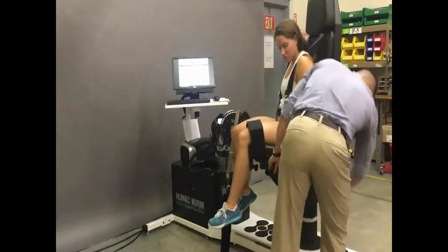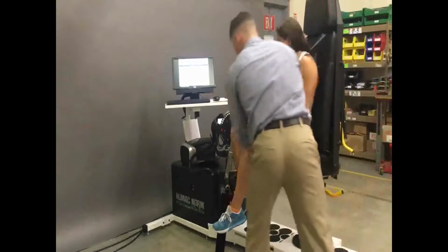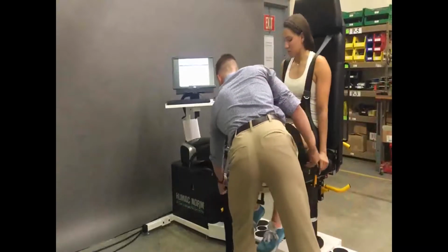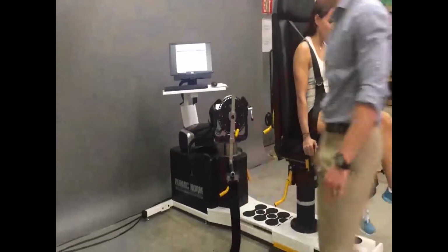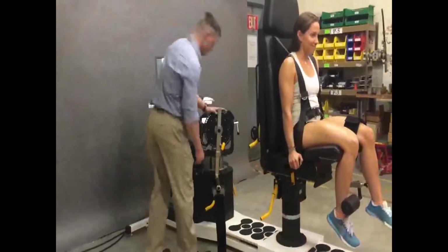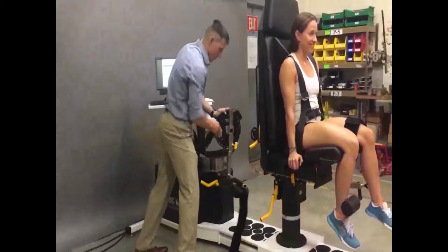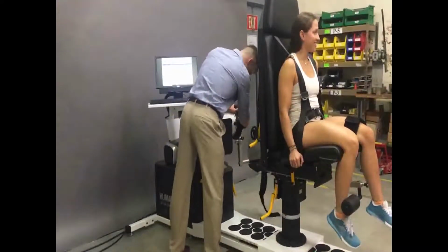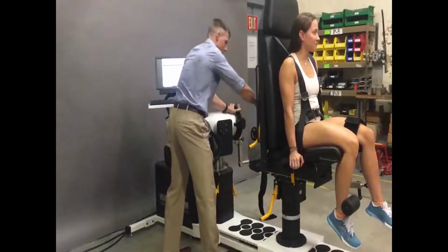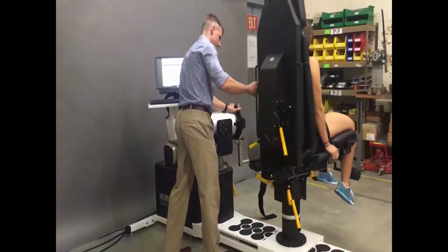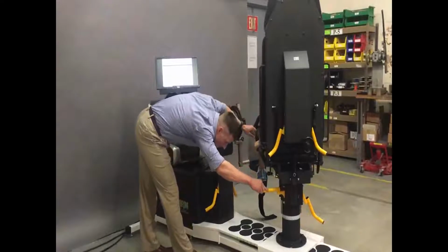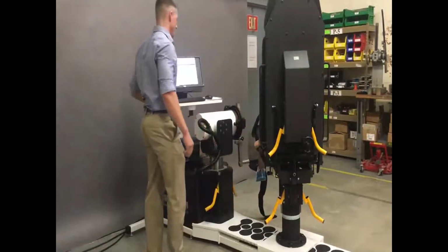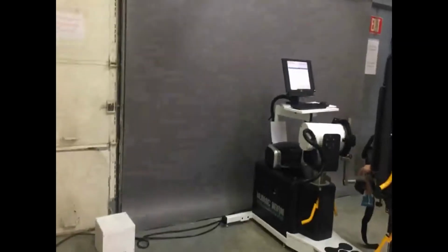Now you can stay on this side of the machine for this next series. Unlock the chair rotation, swing the patient to face the back side. Now stay on that same side. Unlock the dynamometer rotation, swing it well beyond that 40-degree line. Now you can rotate the patient's chair over, lock it in right at the 40, and then from there you can move to the other side.